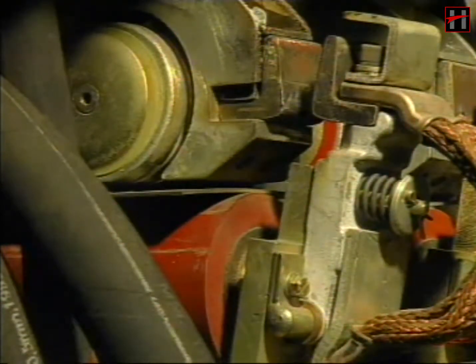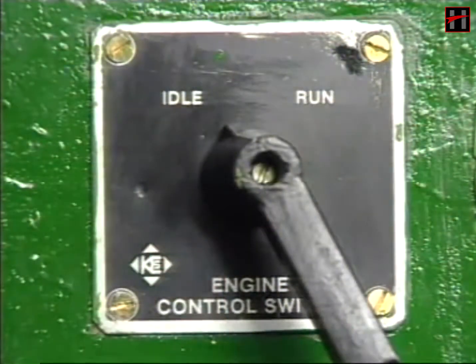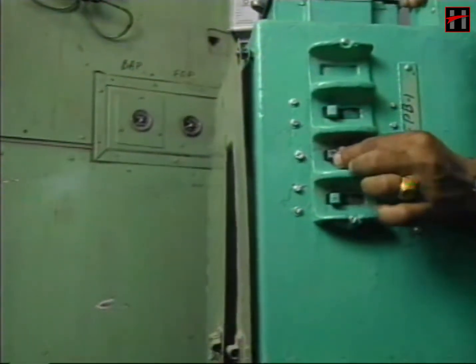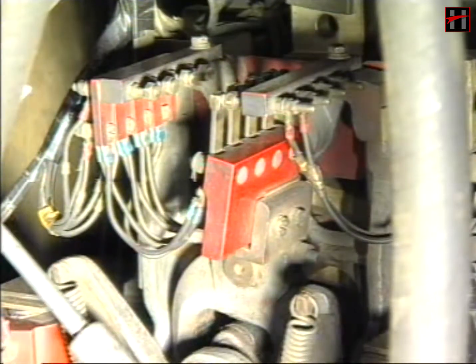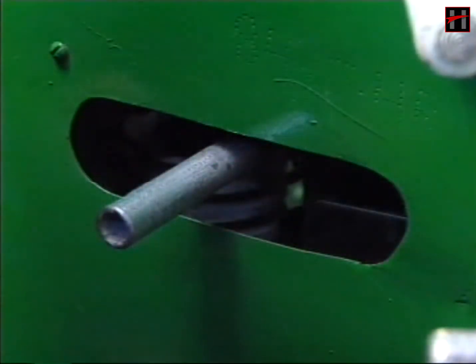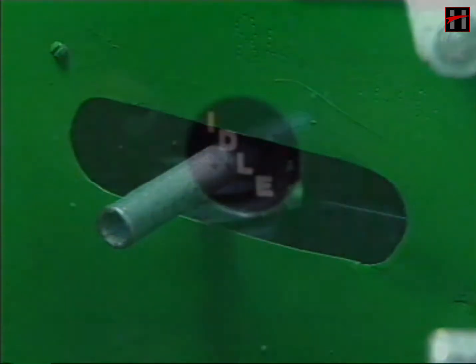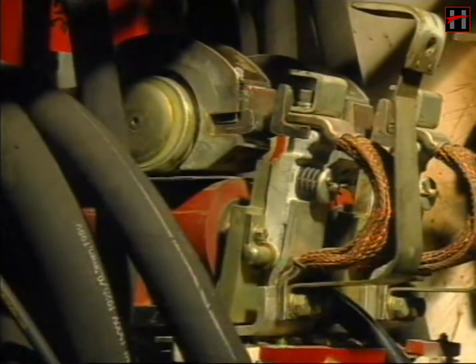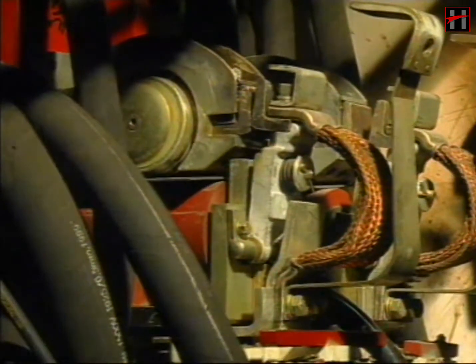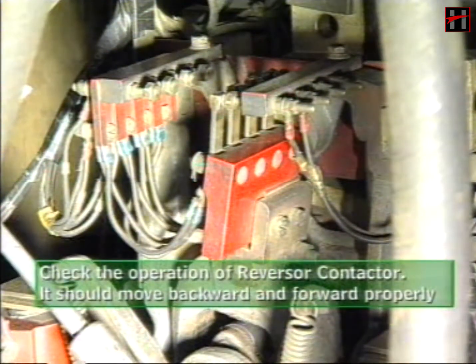Check the operation of the GF contactor. Put the ECS on run, GF switches on both control stands in on position and give direction to the reverser contactor. Put the reverser handle in neutral position and throttle on the first notch. If the GF contactor picks up, the operation of the GF contactor is right. Check the operation of the reverser contactor. It should move backwards and forward properly.